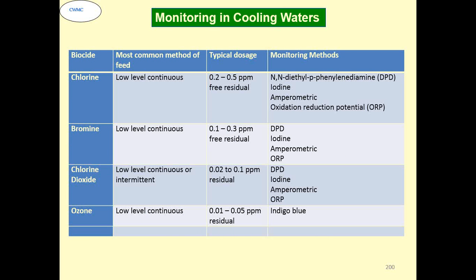Chlorine, low level continuous, 0.2 to 0.5 ppm residual. Bromine, 0.1 to 0.3. The only thing is, if there is any possibility of this water being used for a drinking application, don't use bromine, because bromine is not accepted by WHO for drinking water. Whereas chlorine, chlorine dioxide or ozone, all three are accepted at the drinking water level.